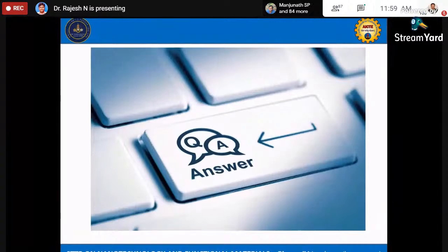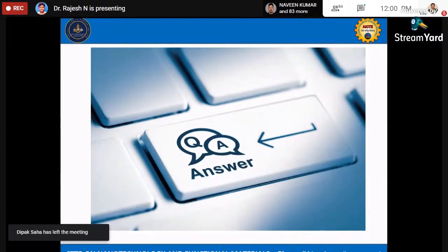So we have a lab, CMTI, which is in Bangalore. They have a very good facility to calibrate the masters. It can be calibrated. We have a setup in our Taylor Hobson facility at Leicester in UK. We can calibrate it. So using the calibrated master, using the calibrated results, we are able to calibrate and prove the machine at site or online.